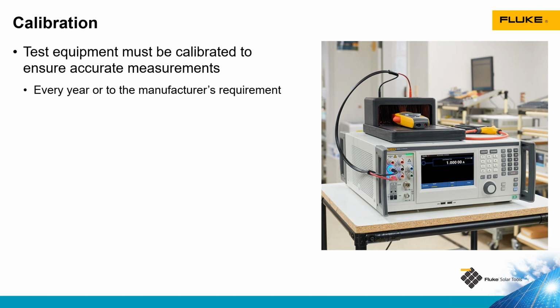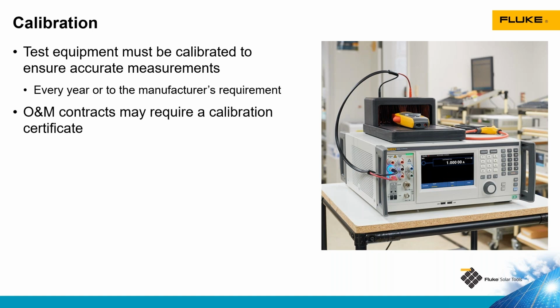Our test equipment needs to be calibrated on a fairly regular basis, and most Fluke tools recommend an annual calibration, and so having it sent out every year to be calibrated. Sometimes when you're doing third-party operations and maintenance, especially if you're doing testing, if an asset is going to be sold, they'll want to make sure that you have a certificate of calibration for your test tools before you go out and do the testing so that they know that the test results are accurate.